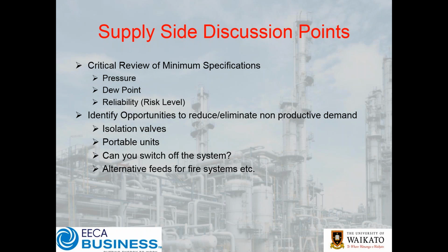It's not like a variable speed compressor that can vary its speed to give you a steady output. Your dew point's going to change just by virtue of the desiccant starting to get saturated. So are you talking about that sort of variability, or being able to maintain a minimum set point? Yeah, I was referring to a maximum set point.